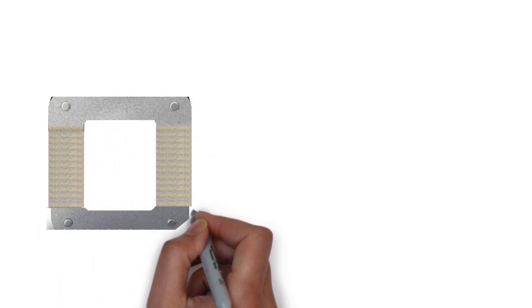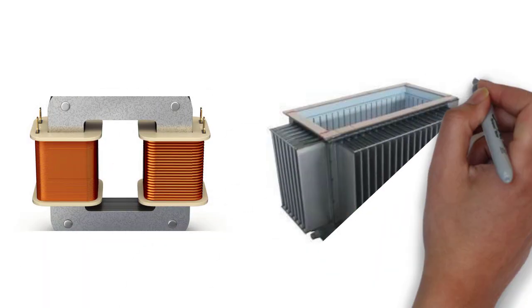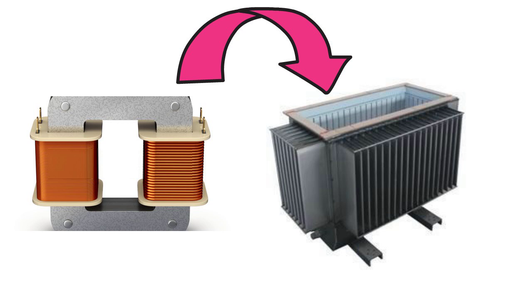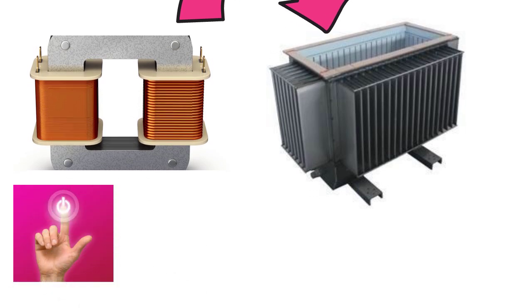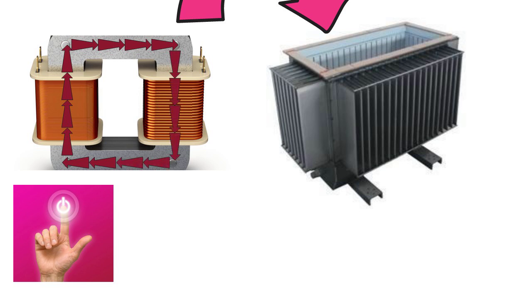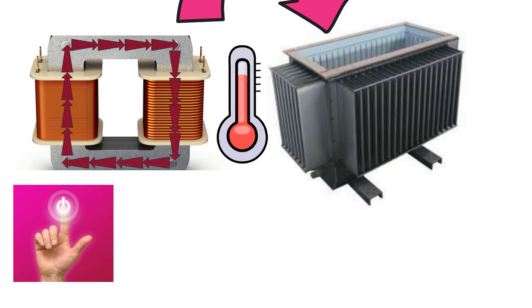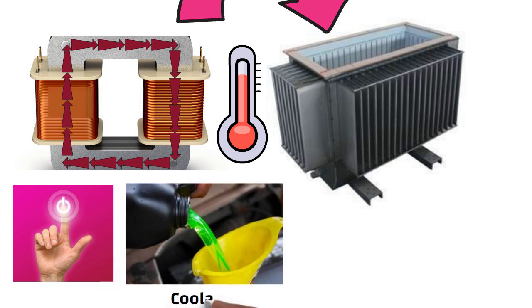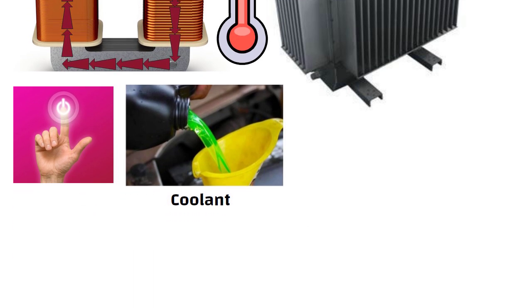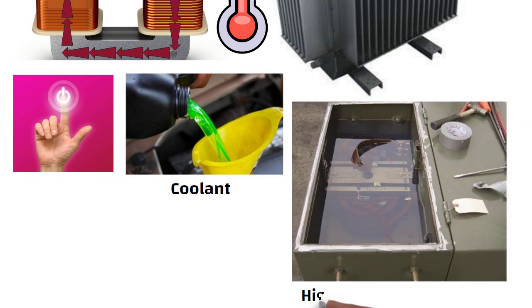Now let us keep this core and winding inside the main tank. And in this condition, if we switch on the transformer, the current will flow through the core and winding and it becomes hot. So to cool this core and winding, we need a coolant here. So this is the reason the main tank is filled with highly refined mineral oil.